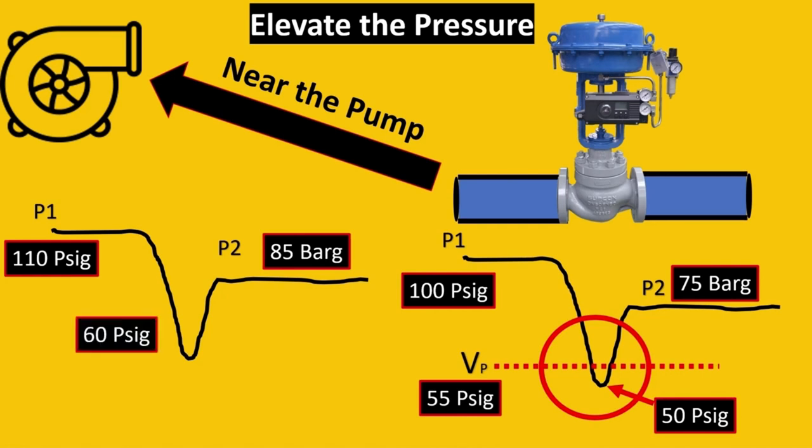My P1 is now 110 psig. I have the same drop of 50 psig, so I get 60 psig here because 110 minus 50 is 60. The amazing thing is, look at the vapor pressure curve - it was 55 psig, so it's going above, and we've saved cavitation without adding anything, just moving the control valve. Isn't it amazing?